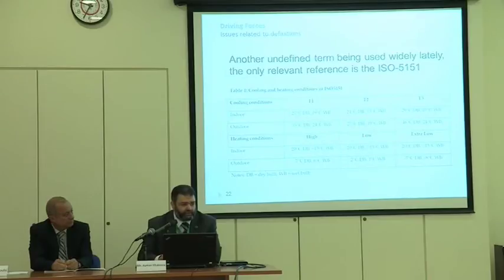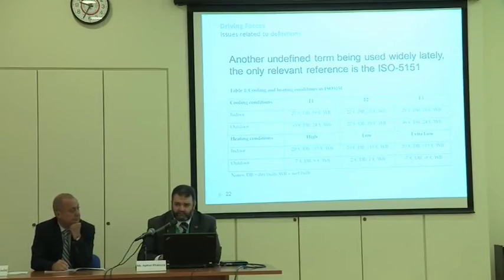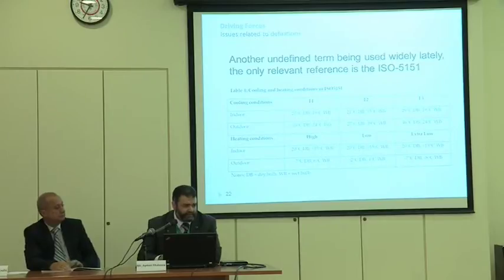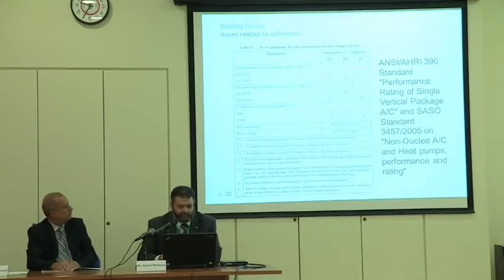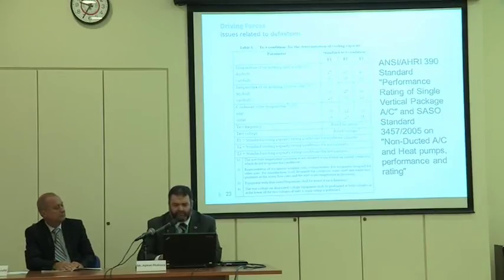We concluded that high ambient refers only to countries who are designing air conditioning units for T3 conditions, which is the 46-degree outside temperature design condition requirement. Many countries have hot climates and high ambient or humid conditions, like South Asia and others, but they don't design for this operating condition. So this is the reference now for what we are calling high ambient. This is the ISO standard, and the ANSI AHRI standard, which is also adopted by SASO — they all adopt the same T3 condition design characteristics, which is 46 outside temperature.